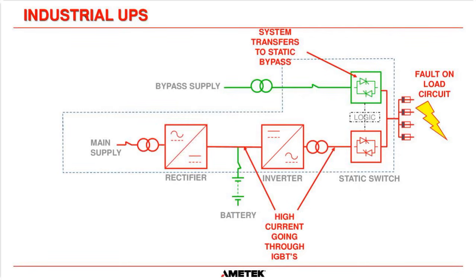And there's just a diagram of what's happening. If we're saying that 120 amps is too much to go through our inverter bridge, which is where the IGBTs are, then we transfer to bypass. It will clear the fault. And then once that fault is cleared and taken care of, you can put the system back onto inverter operation.